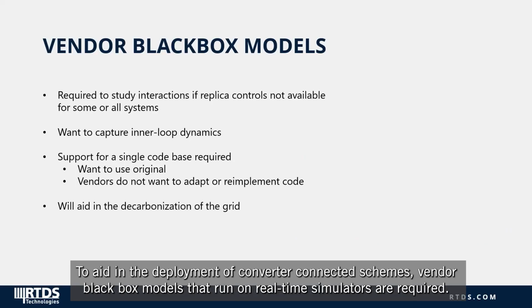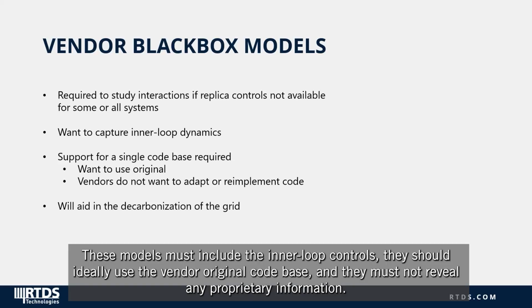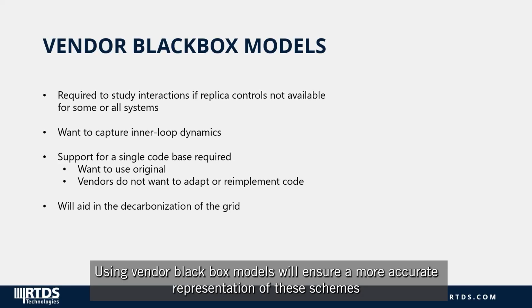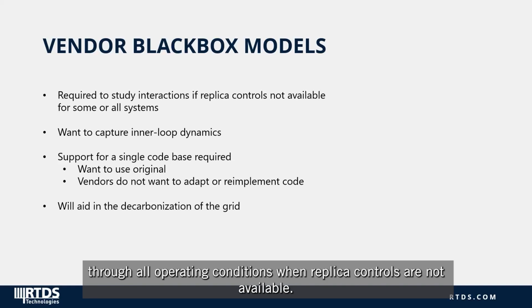To aid in the deployment of converter-connected schemes, vendor black box models that run on real-time simulators are required. These models must include the inner-loop controls. They should ideally use the vendor original codebase, and they must not reveal any proprietary information. Using vendor black box models will ensure more accurate representation of these schemes through all operating conditions when replica controls are not available.